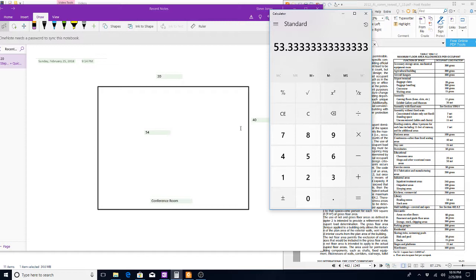The other thing we know is that any time two exits are required, exit signs are required. So each one of these exit doors will have exit signs. And because it has more than 49 occupants, emergency lighting is required. So we have two doors that have to swing out, with exit signs and emergency lighting in this space.